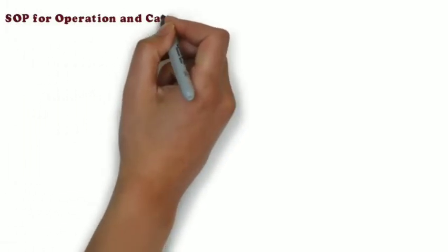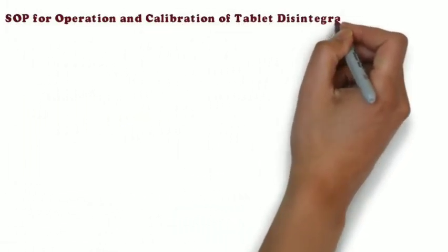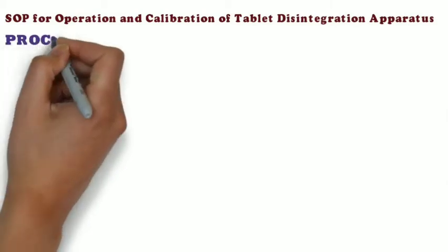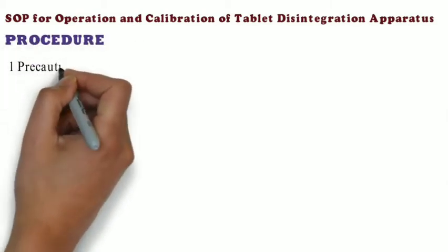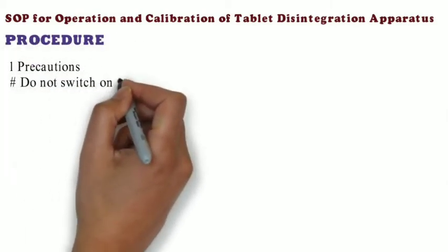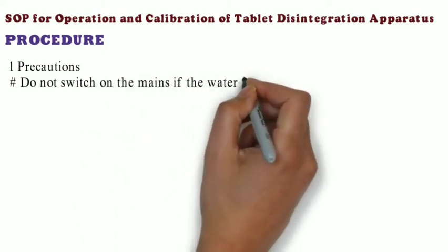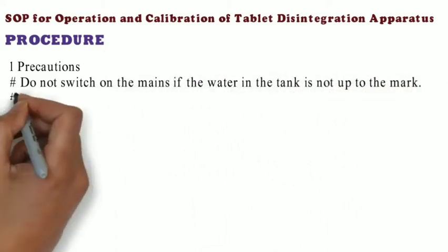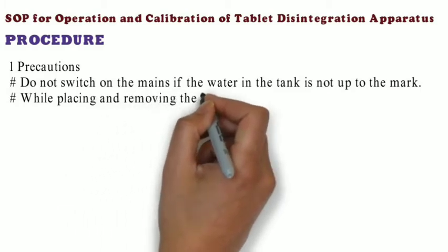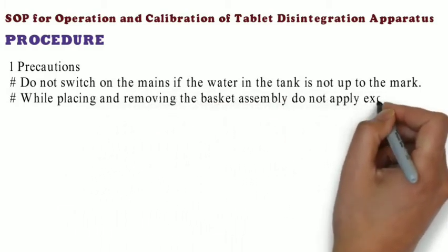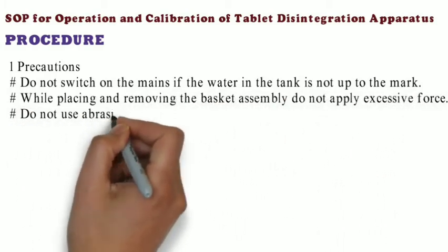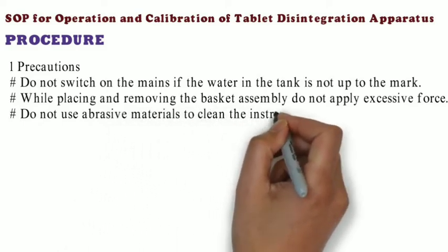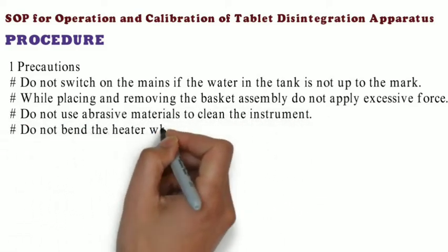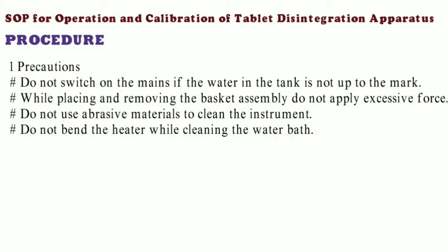Next, the SOP for operation and calibration of the disintegration apparatus. Precautions: do not switch on if the water in the tank is not up to the mark. While placing and removing the basket assembly, do not apply excessive force. Do not use abrasive materials to clean the instrument. Do not bend the heater while cleaning the water bath.